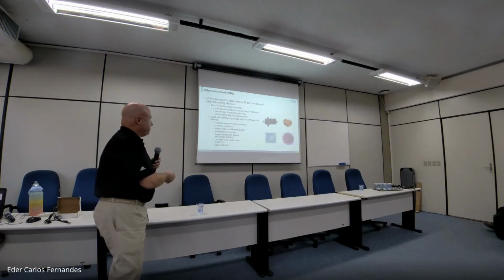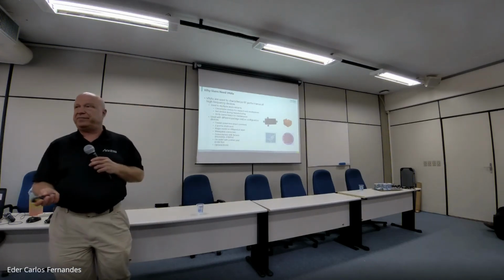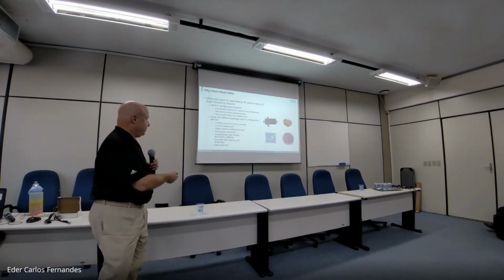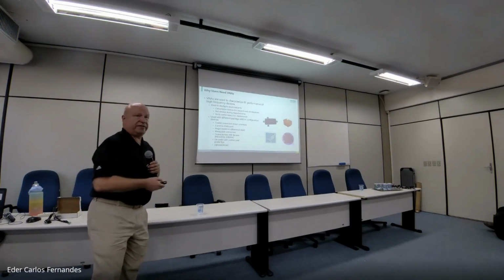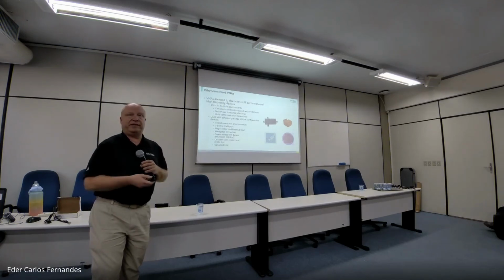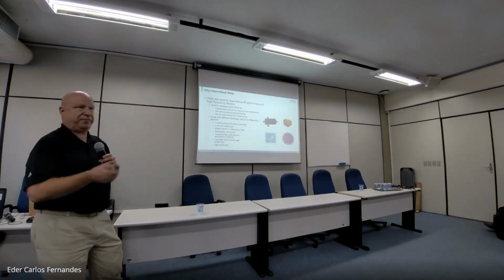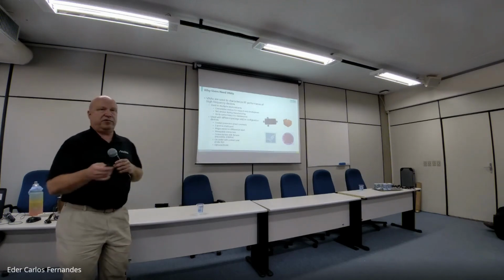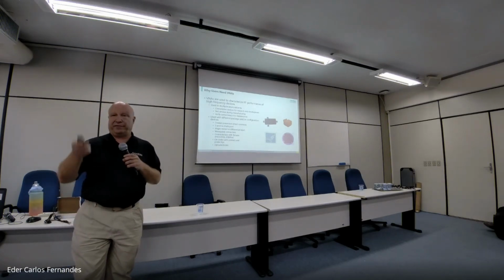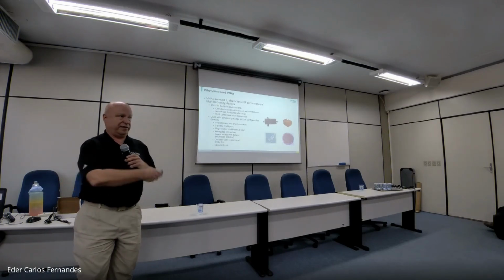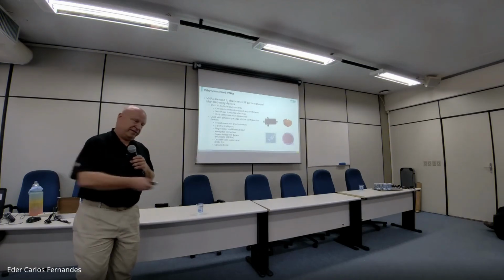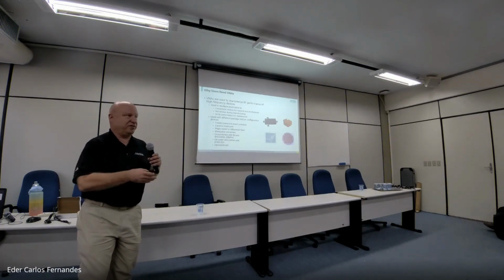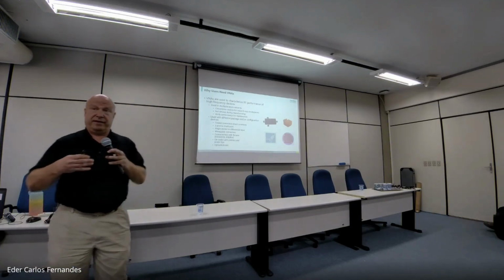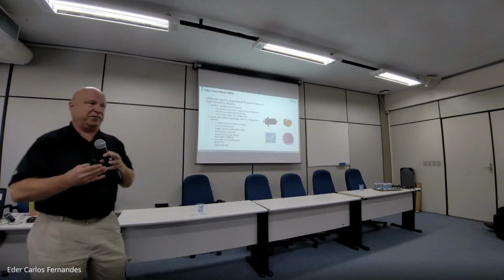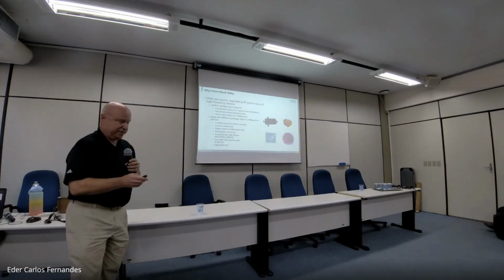So most common is coax, but then we have a lot of other interfaces, waveguide being probably the second highest that we see, and then devices that have no connectors that are either in a fixture or on a wafer substrate. So we have to adapt constantly to these different interfaces through the way we set our reference plane and our calibration. And I'll explain that in a moment, but that's one of the key things about how to run a VNA measurement. It's not just stick the signal into the instrument and measure it. You need to understand everything that's in the measurement path and know how to interface with it and isolate what it is you want to measure out of everything that's connected.